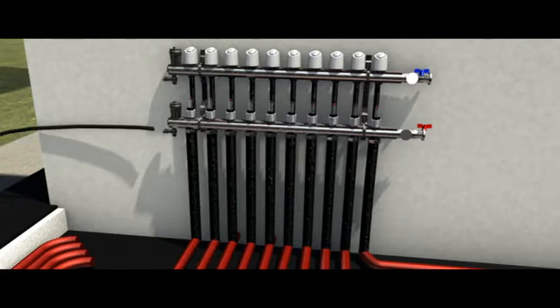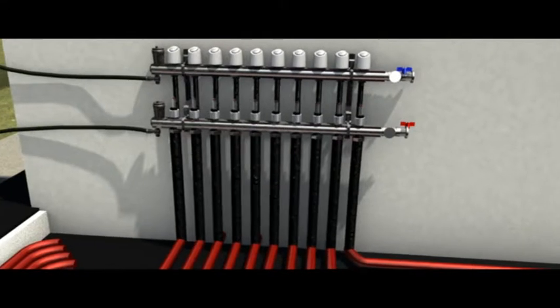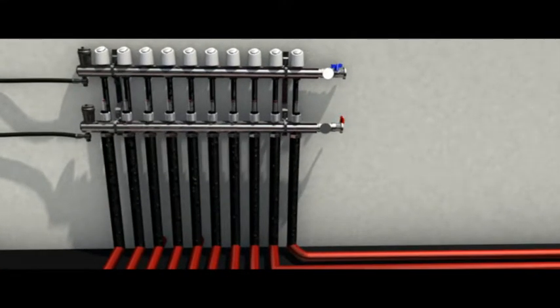First, the drain valve of the flow manifold is connected to a main supply. The drain valve of the return manifold is then connected to a drain hose positioned over a bucket. Next, both shut-off valves on the manifold should be closed. The manifold comes supplied with the flow meters fully closed, thus preventing water from flowing through the underfloor pipes.